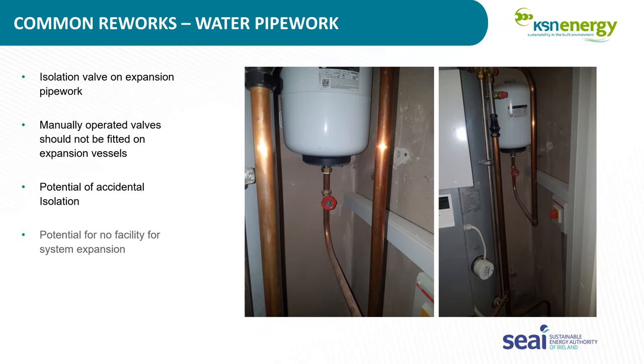I've had it myself where I'd have gone out and someone has said to me, something's not working. And do you know what? We had a leak in the house and I just ran into the hot press and I turned off every valve and I thought I turned every one back on. And it hasn't worked since. Expansion, uninterrupted expansion, is essential for the safe operation of a system. I get that for maintenance, people put them on, so that instead of draining down the whole heating system, if the expansion vessel has to be changed, you put them on.